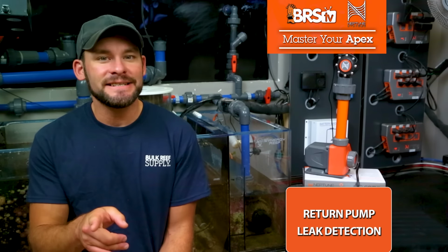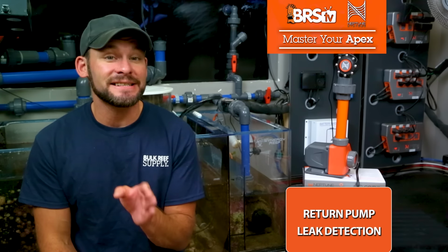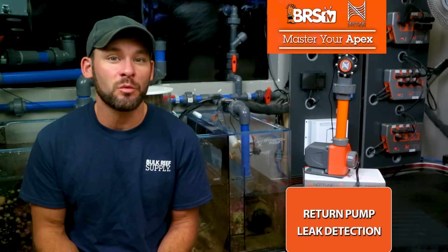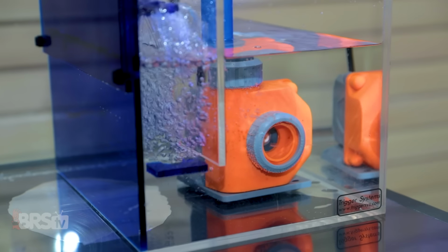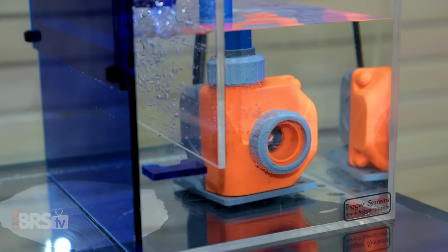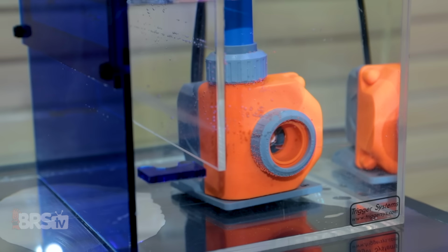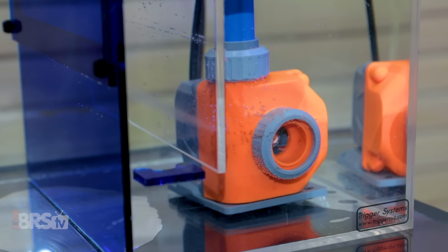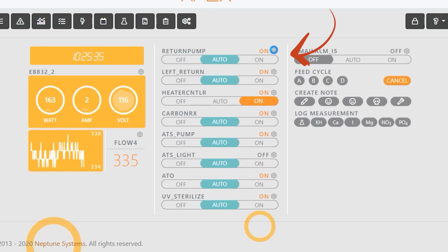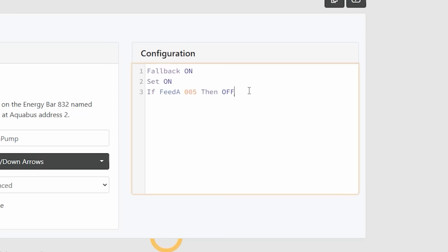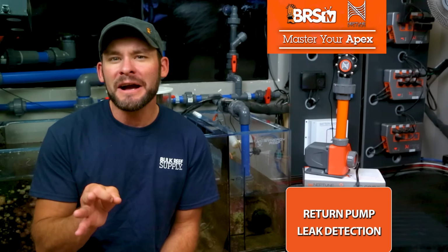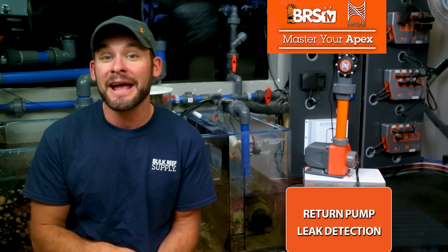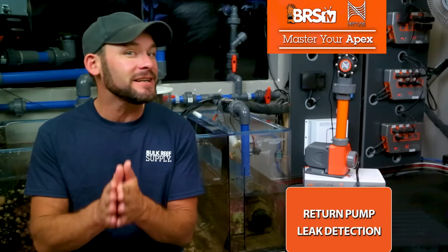So using that LDK task, we just solved getting a text, email, or alert if the leak sensors detect water, but in some cases, I would want to turn the return pump off if a leak was detected to stop the supply of water, in which case, all we need to do is choose the cog icon above your return pump outlet, add in a new line that says, if leak 1 closed, then off.